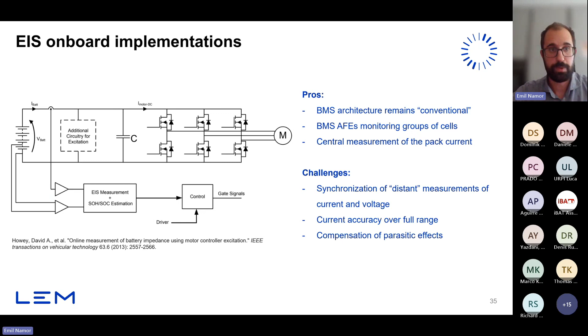Another approach is to have all needed measurements carried out locally, with electronics integrated or distributed in the battery system, eventually at the level of each cell. The advantage is that the proximity of measurements to each cell simplifies the computation of impedance.